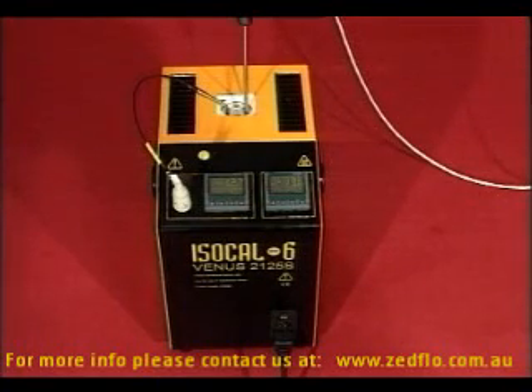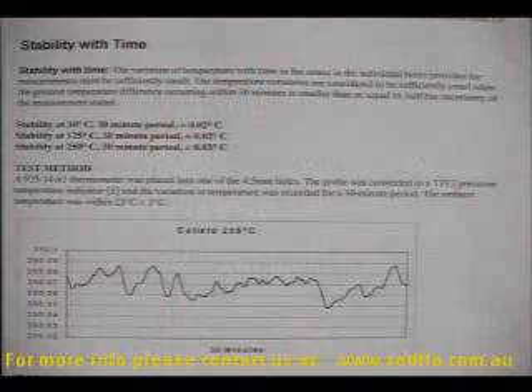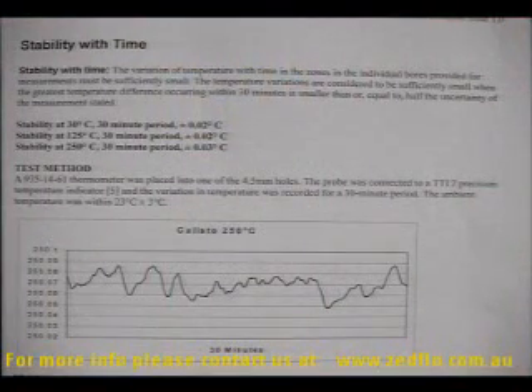As well as the accuracy of our working standards, we need to know the temperature stability and the vertical and horizontal gradients of temperature in the insert. We have made and issued an evaluation document. Here are some of the tables from this document to show you the overall performance of this metal insert in the Isocal 6. Here we see the stability of one of the Isocal 6 products, the Callisto. It is working at its maximum temperature of 250 degrees Celsius. It recorded the absolute temperature inside the insert for a period of 30 minutes. The temperature variation is less than plus or minus 0.02 degrees Celsius, 20 millikelvins.